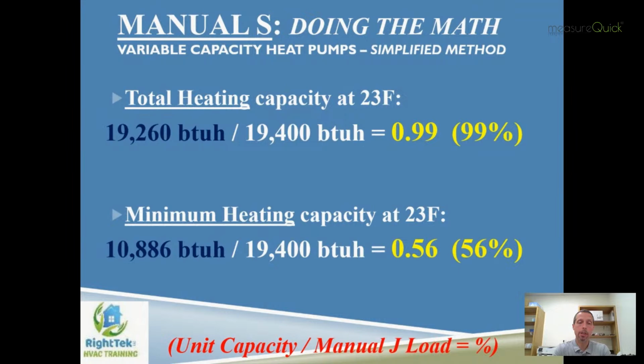But I also need to look, this is the new part, at the minimum heating capacity output, again, at design temperature, 23 degrees, which now is only 10,886 BTUs per hour. And you'll see that that's meeting about 56%. And what the Manual S is telling us here is that it should be less than 80%. And this is kind of a weird concept to understand, but a couple of the major OEMs really push this.